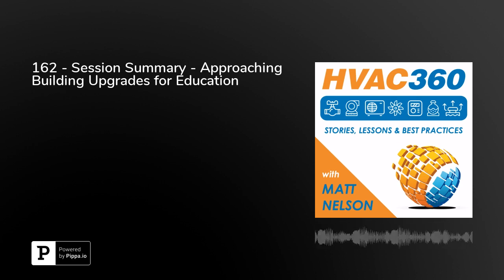Maintenance staff, they want it to be easily maintainable. They want the life expectancy to be good. Same with the people at the university. Everybody prioritizes these categories differently. So that is how that worked out. Based on the scoring, the winner was a VAV with demand control ventilation. All right, not really exciting, but I think the important point was that there were people around the table that had different priorities than the engineers, who may be just looking at energy efficiency, and that if you get the right options with a standard system, you can really make that system energy efficient.